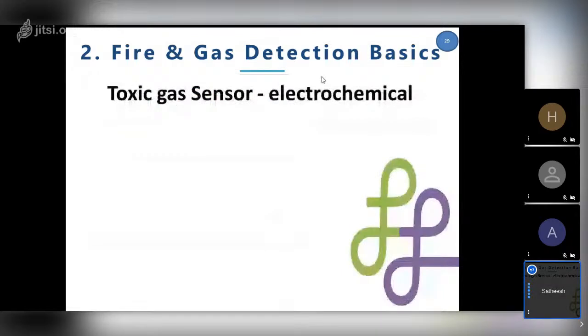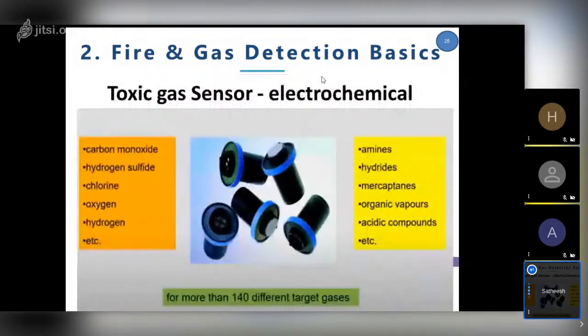For the toxic gas sensor, the technology is called electrochemical. This is the only technology currently available, so it's very easy to understand. Electrochemical sensors are used for detecting toxic gases like carbon monoxide, hydrogen sulfide, and chlorine. We have around 250 gases depending on the industry. Each industry has its own gases based on the product they use or produce, but predominantly H2S, hydrogen sulfide, is the most common in the oil and gas industry. It's the most killer gas, and we target 90% H2S under the toxic category.